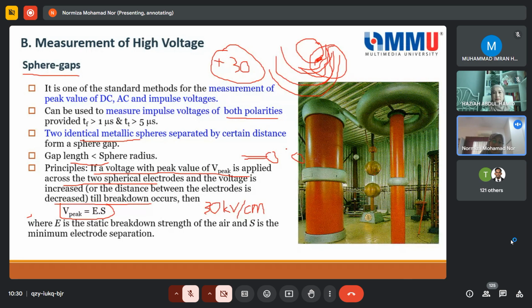smaller size, because if it is too big, then this handle or shank here will need a lot of adjustment. It means that it may not have good strength to support this big sphere horizontally. But when you want to arrange it vertically, it can be a larger size, because even though it's heavy, it can be supported vertically: one sphere is on the ground and you just have to support the other one only, connected directly. Of course, this should have the structure to support it. And then there's a wire, or cable, coming from the resonant transformer here.